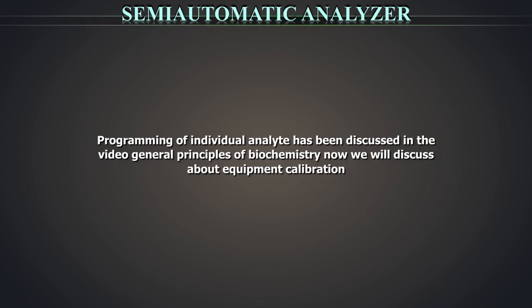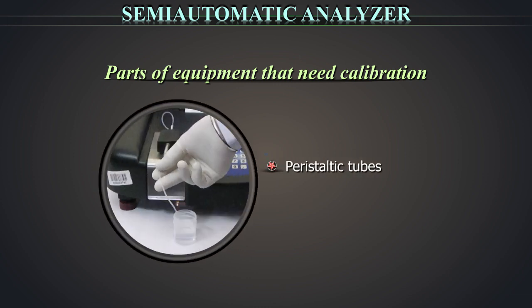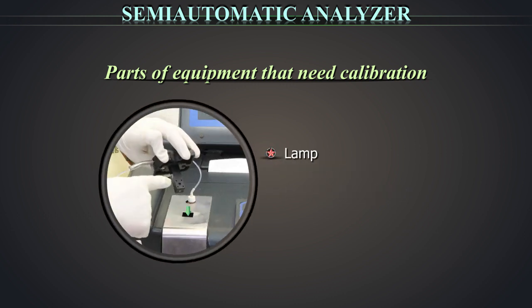Programming of individual analytes has been discussed in the video on general principles of biochemistry. Now we will discuss equipment calibration. Parts of this equipment that need calibration: the peristaltic tubes can grow weak and lose their elasticity over time. The pump that aspirates may go weak and may need readjustment. The lamp inside has a specified life, generally 2000 hours. If you are using your equipment for 4 hours a day, the lamp will need replacement in 500 days, which is less than 2 years. The cuvette or the flow cell will get dirty and will need to be cleaned or replaced. The filters also have a specified life and also require change.